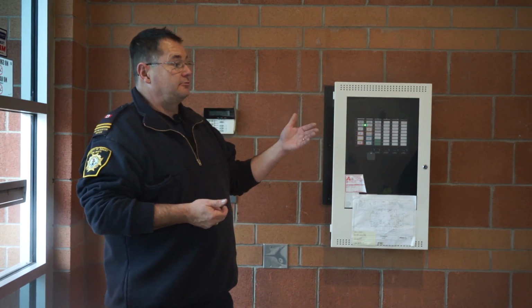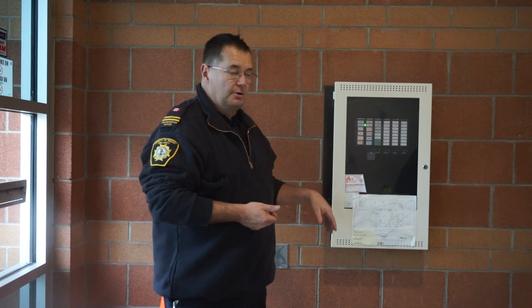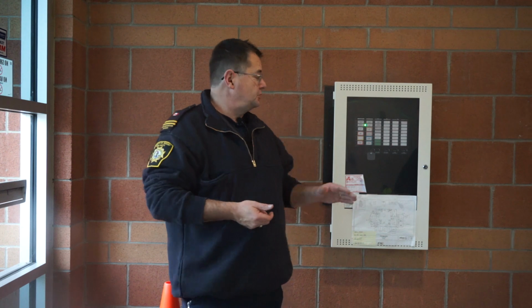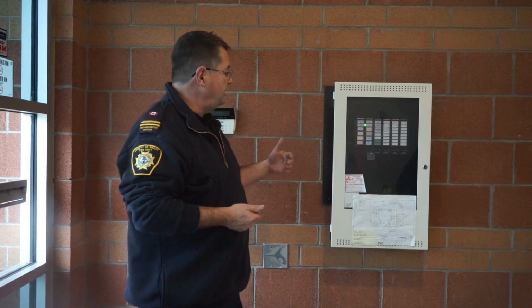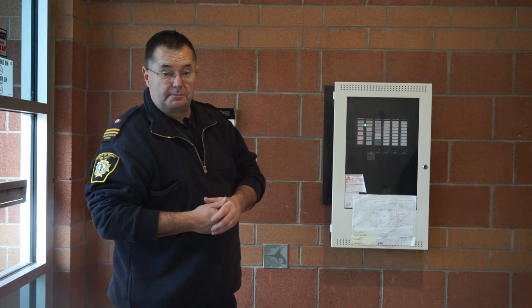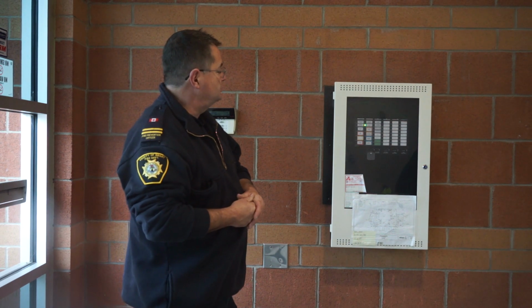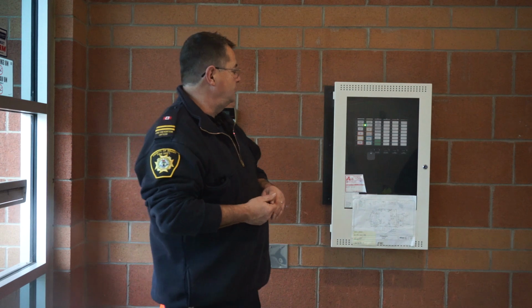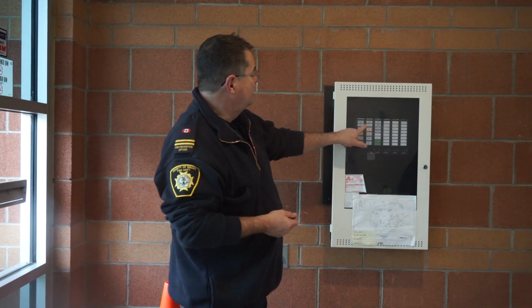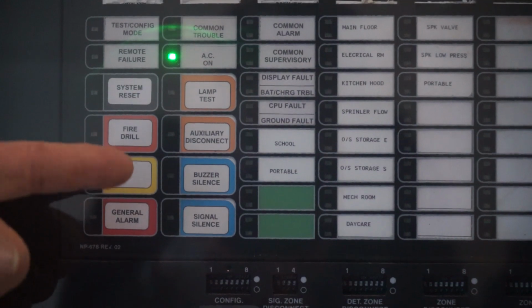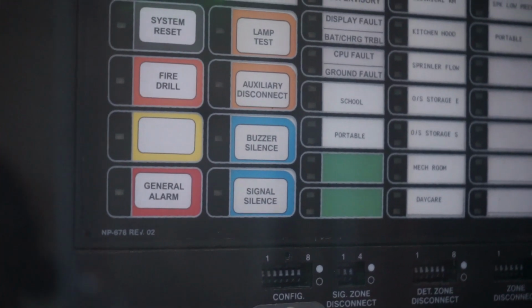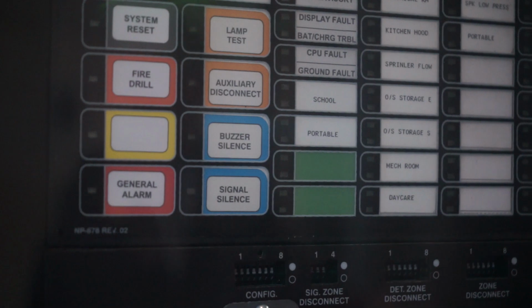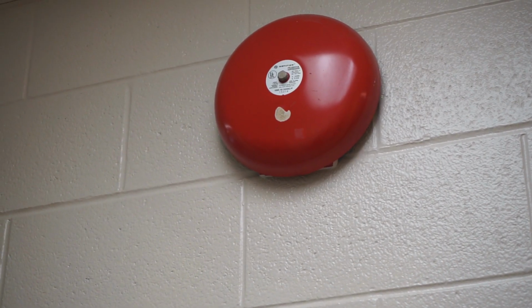Because this is an elementary school with numerous classes, this building requires a fire alarm system. As part of the inspection, the fire alarm has to be inspected annually and every day through the fire safety plan that is written for an assembly occupancy. It needs to show and dictate that some individual in the organization must come and check every day that the green power light's on. What that means is that the power supply to the fire alarm is in place and the fire alarm is serving the building.